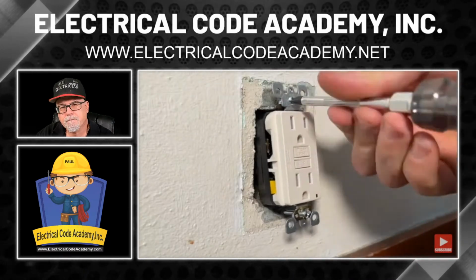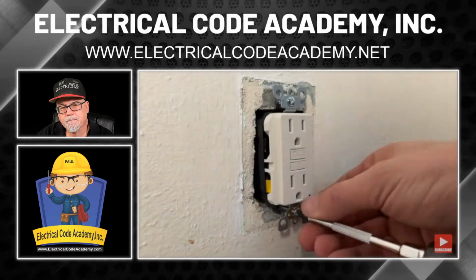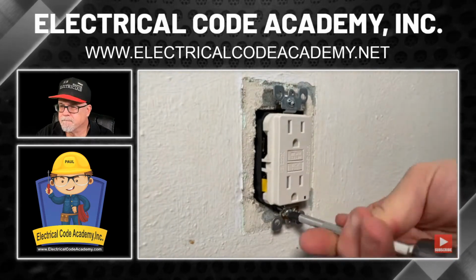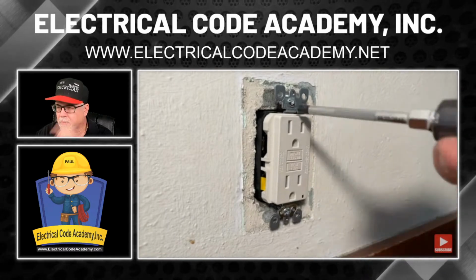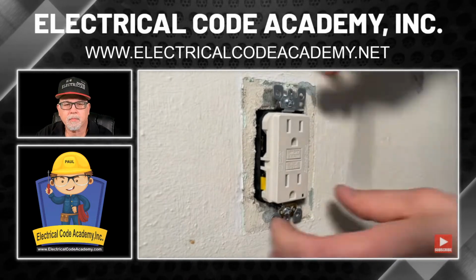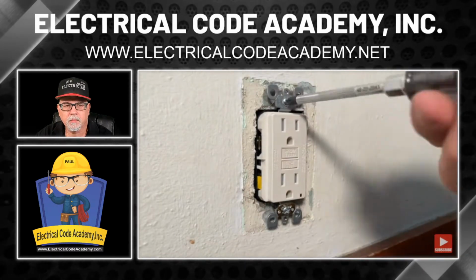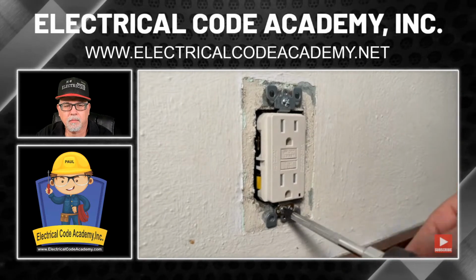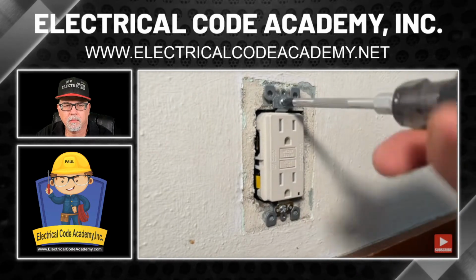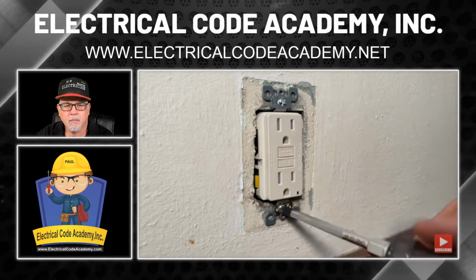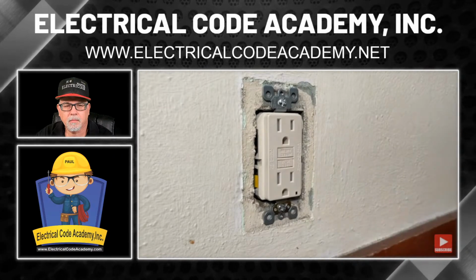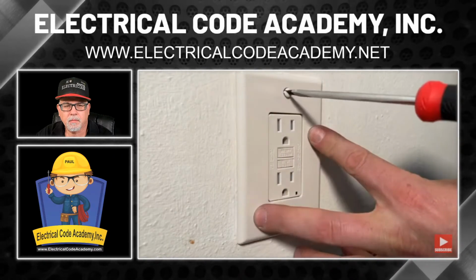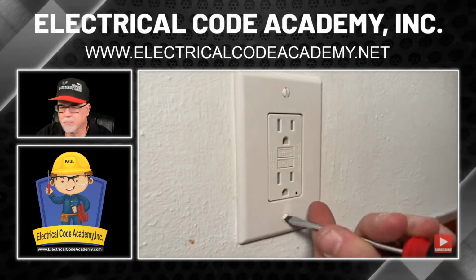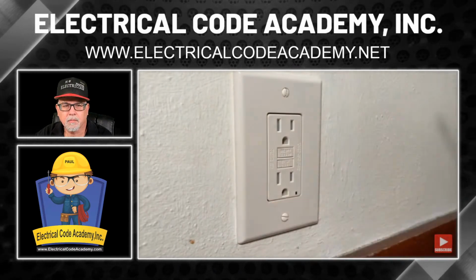Just a couple more screws and we'll be done. So we'll reinstall the mounting screws. I work back and forth, and also make sure that the receptacle is centered so you don't get it tightened and kind of cockeyed in the box. Now once you have that tightened down, we'll do a standard Decora faceplate and then tighten down both of the screws. Then we'll test it out.